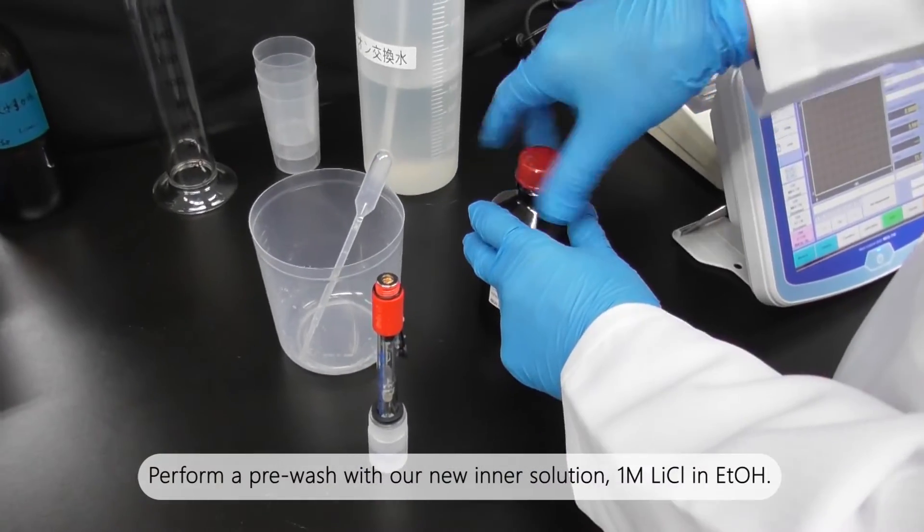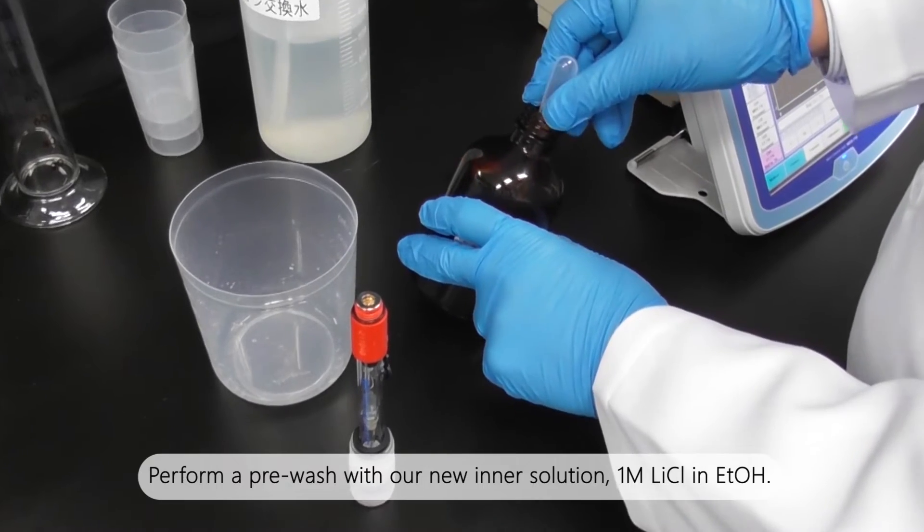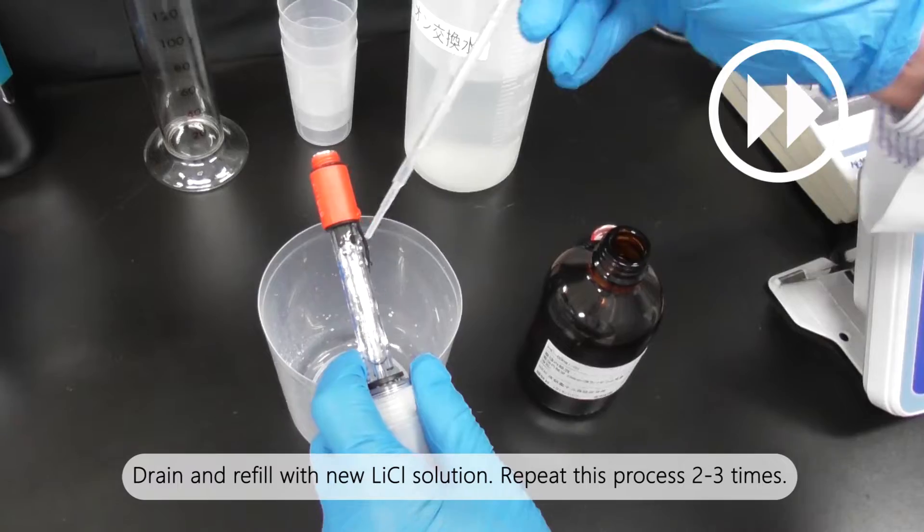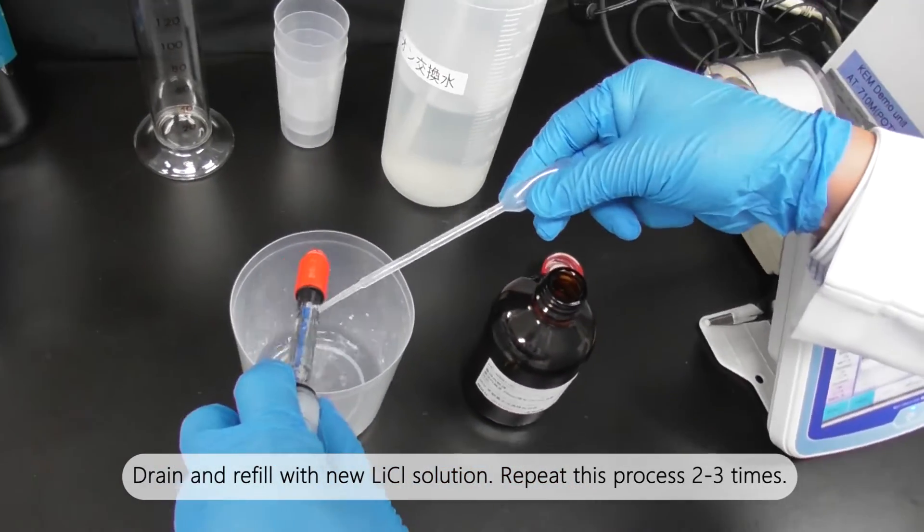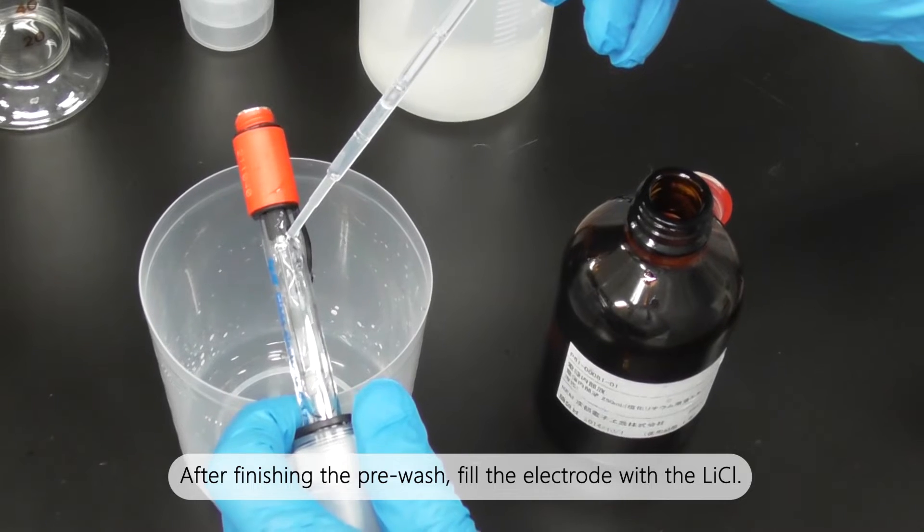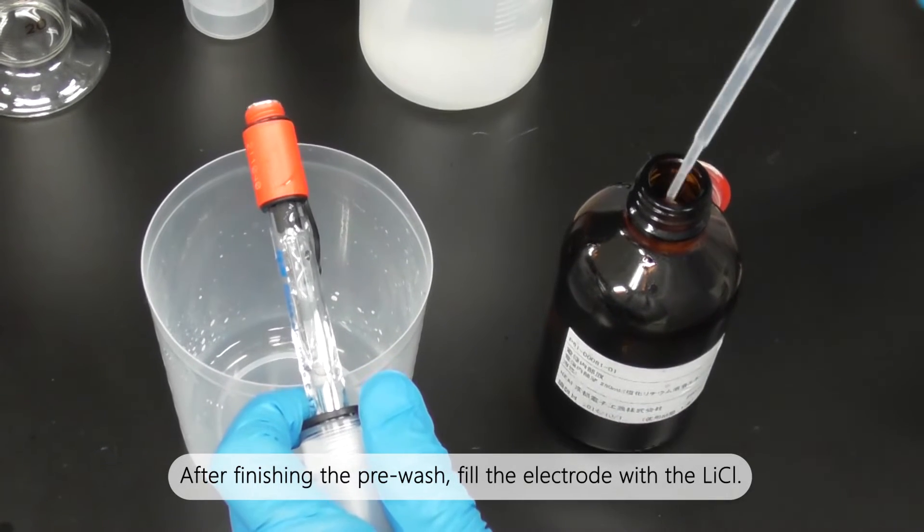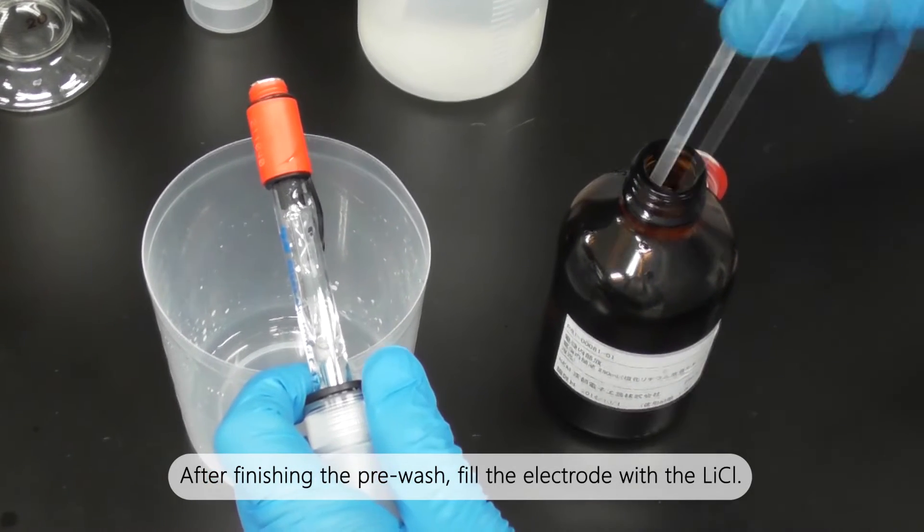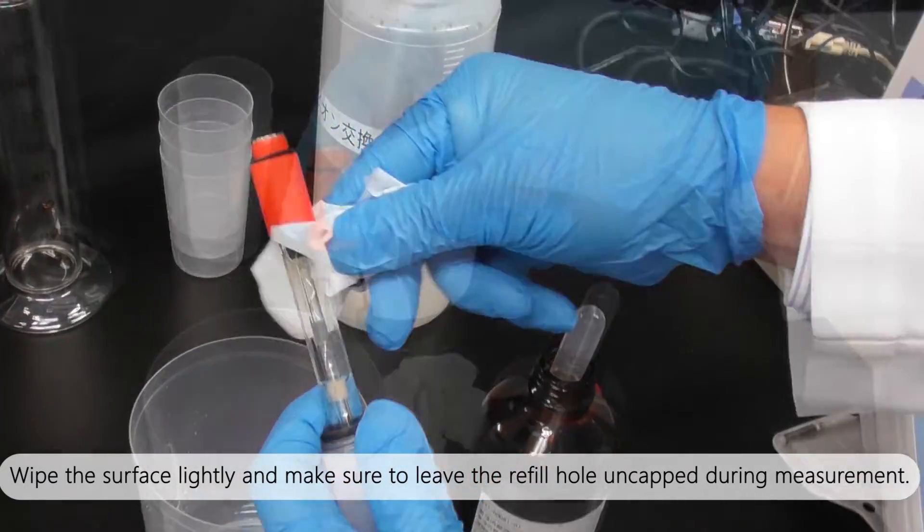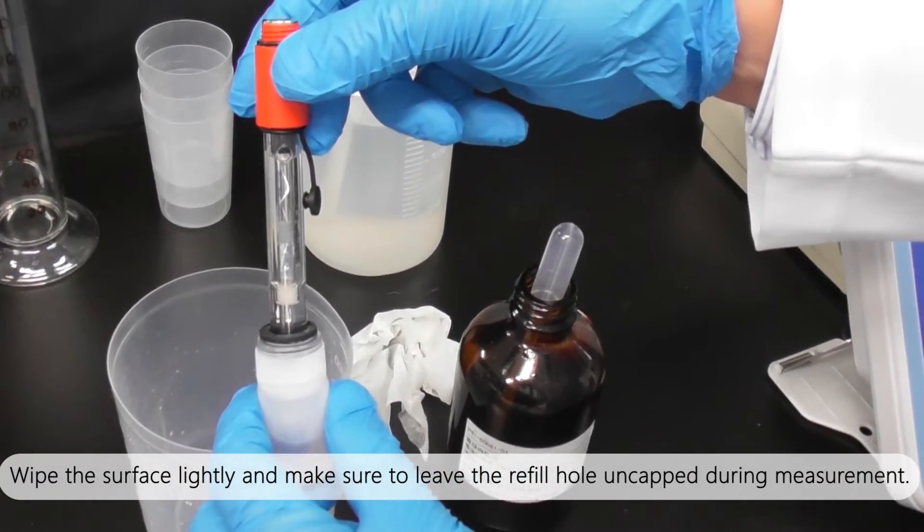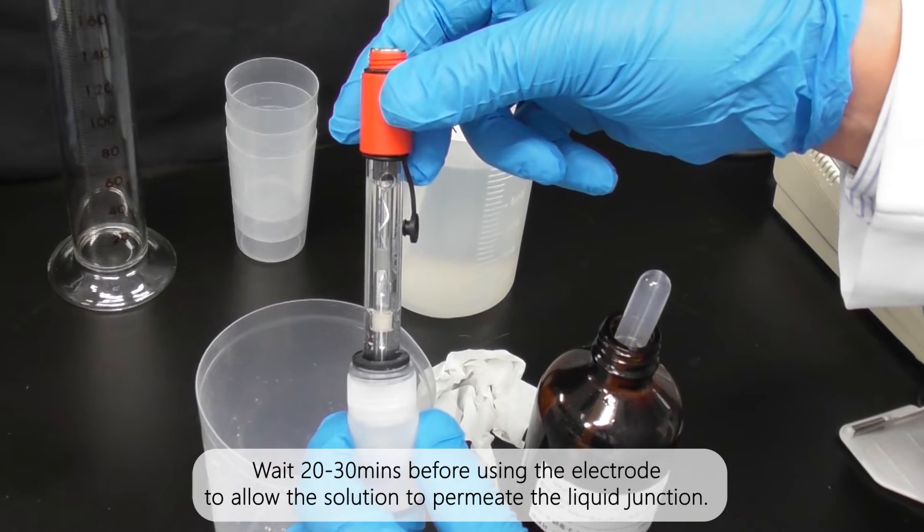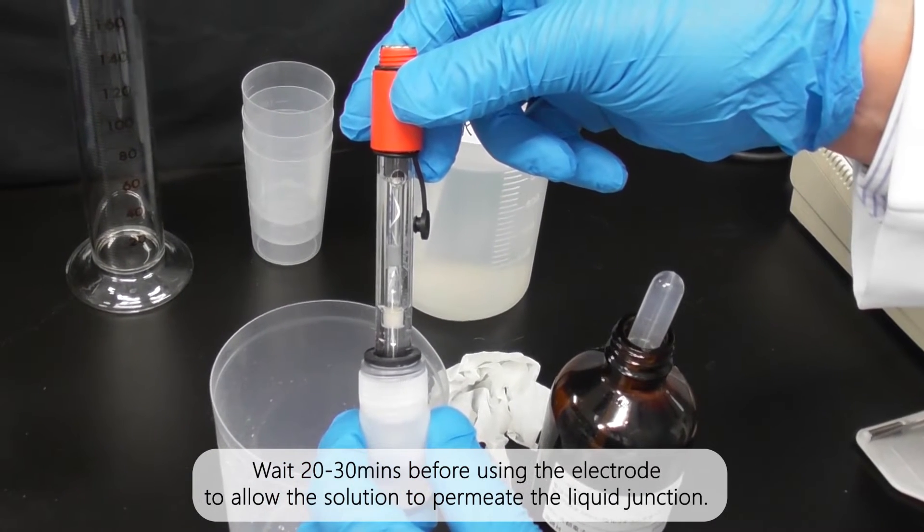Perform a pre-wash with our new inner solution, one mole lithium chloride in ethanol. Drain and refill with new lithium chloride solution. Repeat this process two to three times. After finishing the pre-wash, fill the electrode with lithium chloride. Wipe the surface lightly and make sure to leave the refill hole uncapped during measurement. Wait 20 to 30 minutes before using the electrode to allow the solution to permeate the liquid junction.